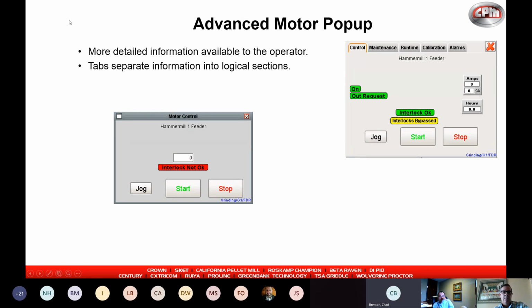This is a concept we've done that we're pretty excited about—we're calling it our advanced motor pop-up. Currently, when you run a motor in manual, this is the pop-up you receive: start, stop, jog, and if it's speed controlled, you can type in your speed from 0 to 100%. But with the advanced version, we're putting more information on the main screen.